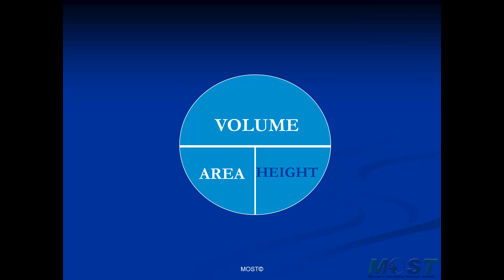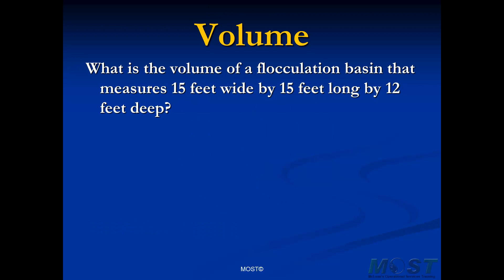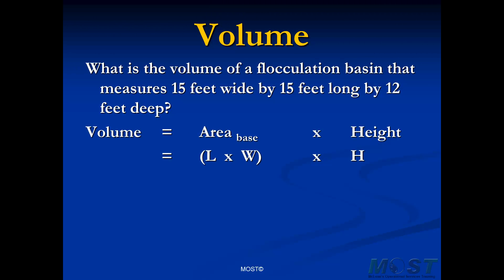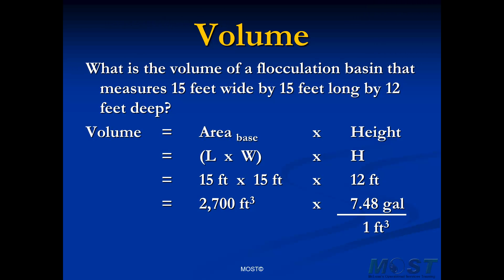So let's find that volume. We're going to use another one of our five MOST formulas: volume equals the area of the base multiplied by the height. For our flocculation basin, the area of the base is length times width, multiplied by the height or depth. That's 15 feet by 15 feet times a depth of 12 feet, giving a volume of 2,700 cubic feet. However, we want to express that volume in gallons for compatible units, so we use our conversion factor of 7.48, and our volume becomes 20,196 gallons.